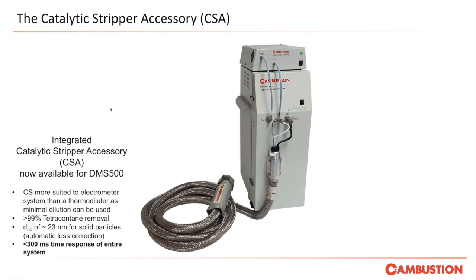It just needs a source of oxidant gas, i.e. oxygen. This removes more than 99% of tetracontane, C40, and the system as a whole has a particle loss profile that roughly equates to a D50 of 23 nanometers. And there is a loss correction built in to the software, which I'll come on to later. The take-home message is, by adding this accessory, we have not compromised the time response of the DMS. We can still have a time response, including the heated line, of 300 milliseconds.